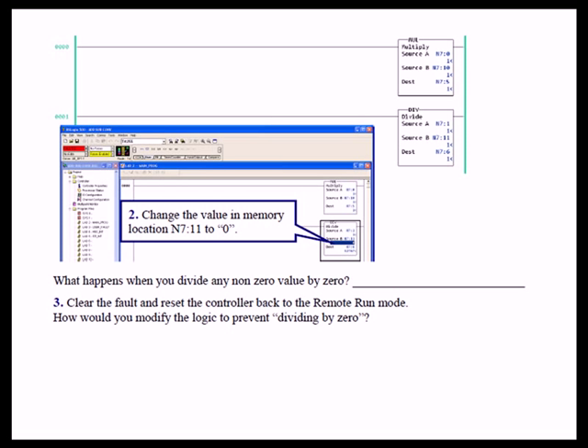We wanted to remind you of a characteristic of a programmable logic controller that's not true when you do math on paper. We know that if you divide any value by zero the result is infinity. However, we cannot represent a value any larger than 32,767. So in a PLC, what happens when you divide any non-zero value by zero? It equals infinity and faults the processor. So we had to clear the fault, reset the controller back to the remote run mode, and ask you how would you modify the logic to prevent dividing by zero?